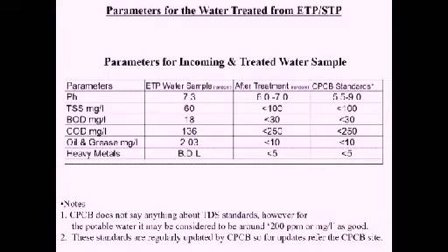These are on the basis of the basic parameters available from CPCB sites. So you could see the CPCB standard says pH should be roughly around 5.5 to 9 for the treated water. Then the TSS, or the total suspended solids quantity, should be less than 100. The unit is milligram per liter. It is roughly similar to ppm, parts per million.